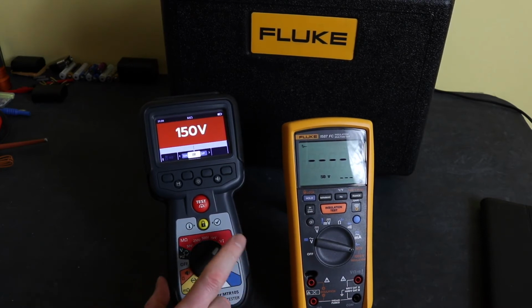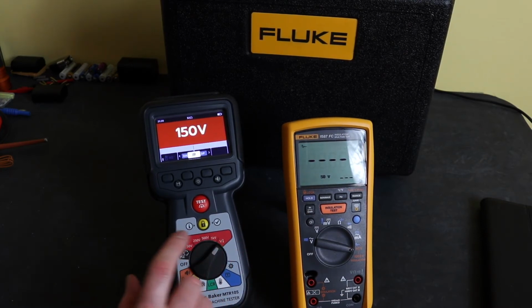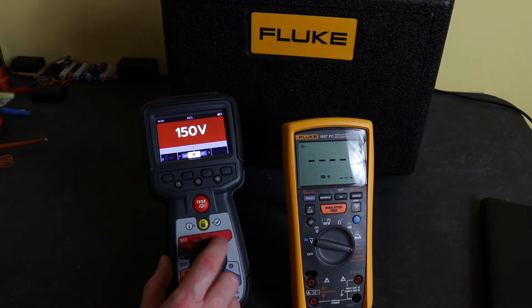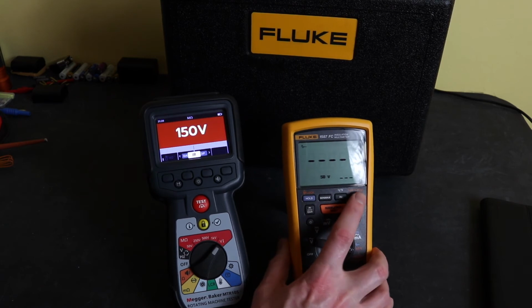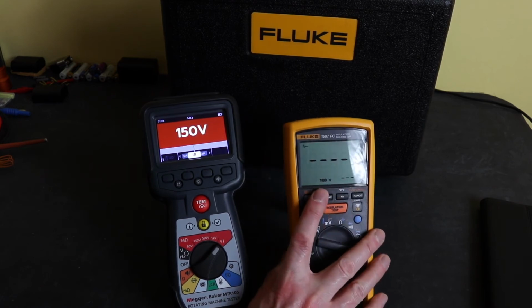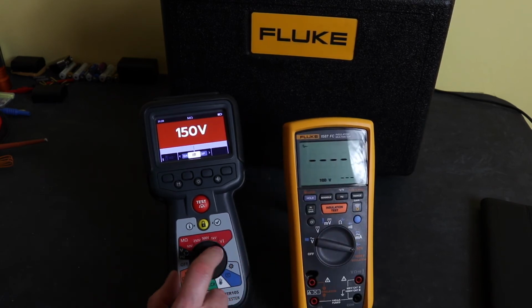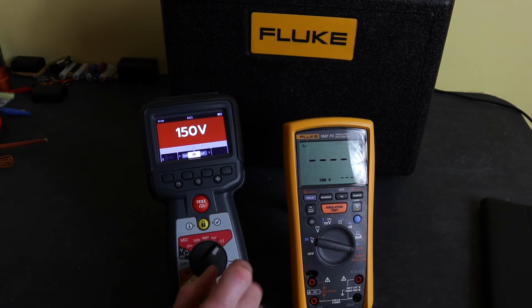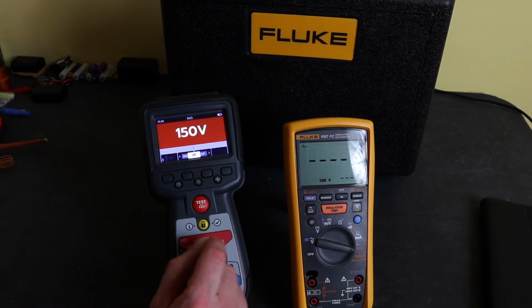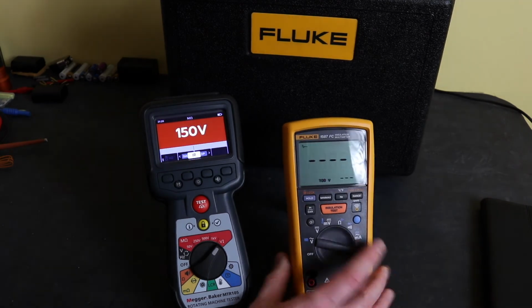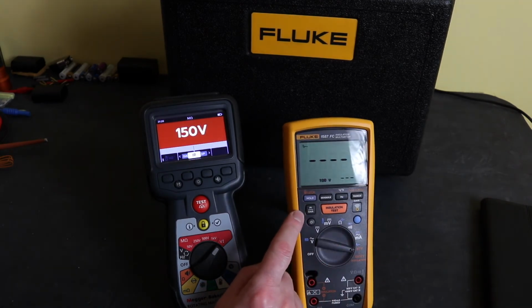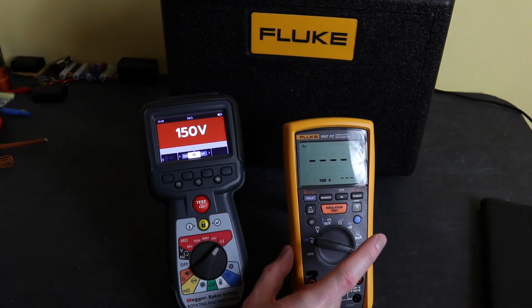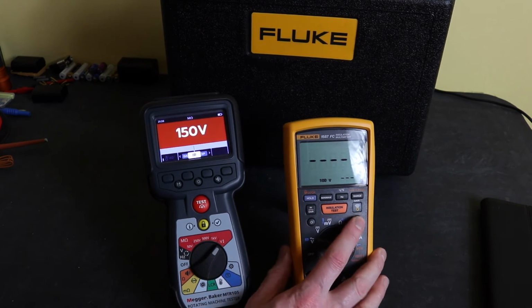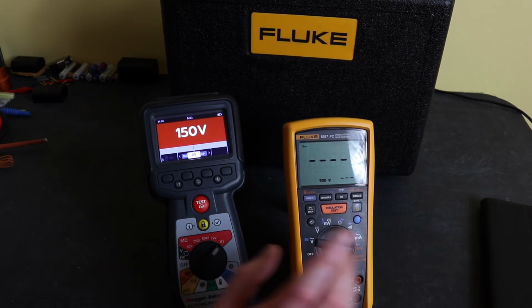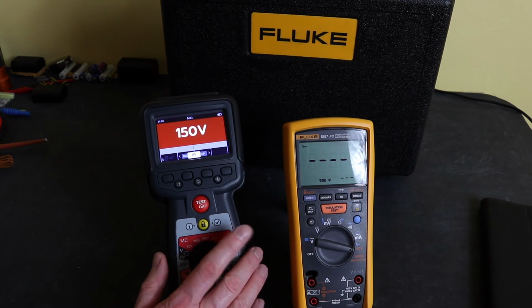As an extra, you have a variable voltage function, which you can set anywhere between 10 and 1000 volts. So whilst this has the 100 volt function there, you obtain the same voltage from the variable function on the Megger. As well as the test functions here, on this you have PI and DAR testing, and you also have a smoothing function, which is the blue button here that I turned on previously. The Megger has no smoothing function.